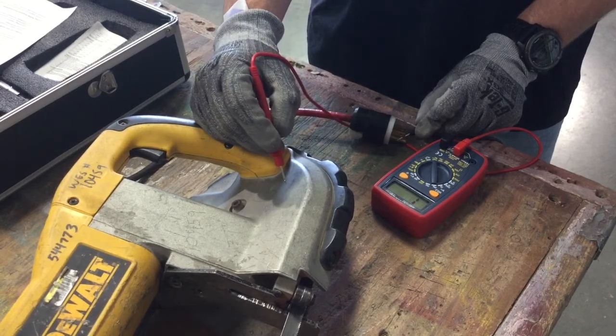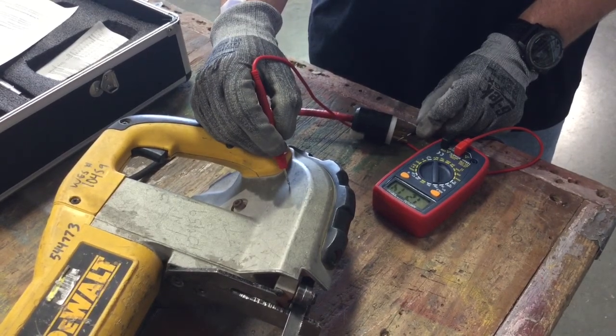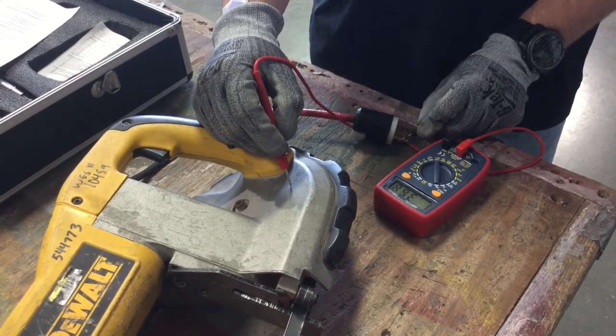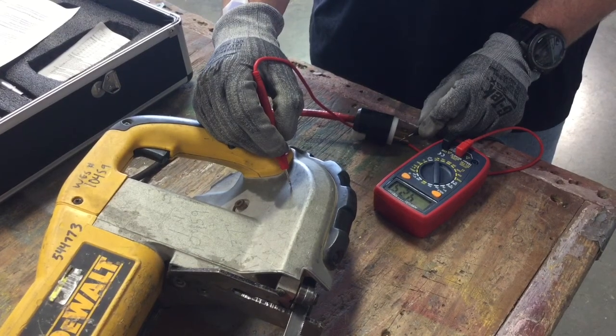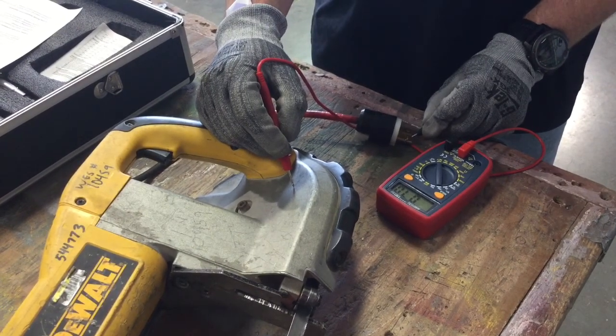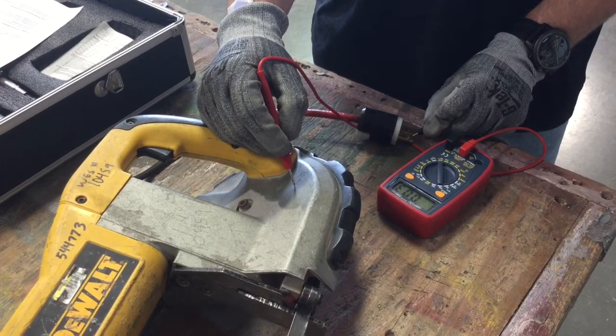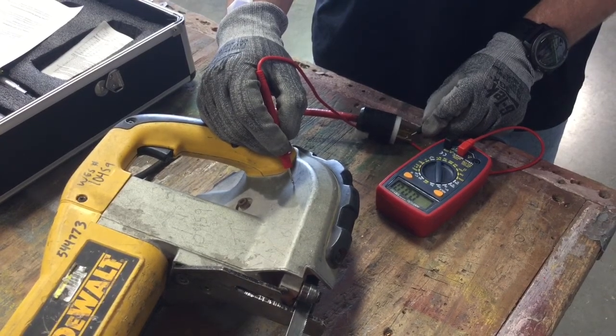Test grounding conductor on tools and equipment for continuity by using a multimeter on the ohm setting. Place one probe of the multimeter on the tool or equipment ground prong and the other end on metal inside or on the tool. There should be continuity.